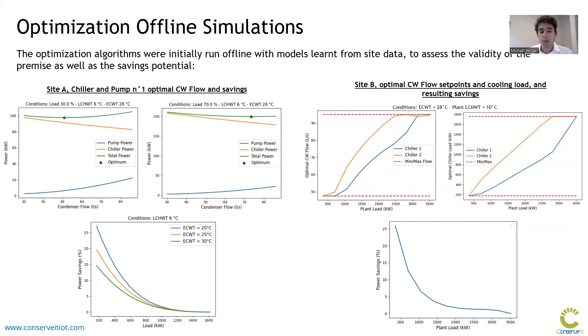These models were then used to run the optimization described earlier. Initially, offline simulations were run to assess the validity of the premise as well as the savings potential of the approach. For site A on the left, we have a case where condenser flow optimization only is examined. The two top graphs show the optimum condenser water flow that minimizes both chiller and pump power — for a load of 30 percent and a load of 70 percent — and in each case the optimum condenser water flow is found to be different. This highlights that a typical strategy keeping condenser flow constant may not be optimal at all times. Below, the calculated savings compared to keeping condenser flow at design value show good savings up to 25 percent depending on the entering condenser water temperature and load conditions.